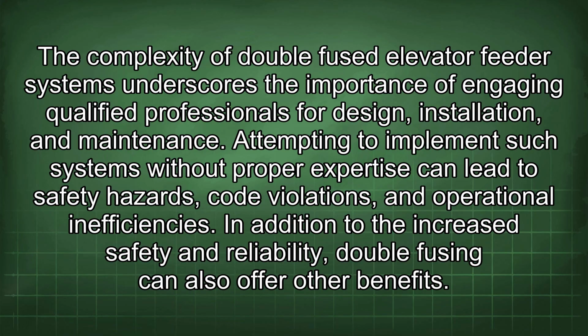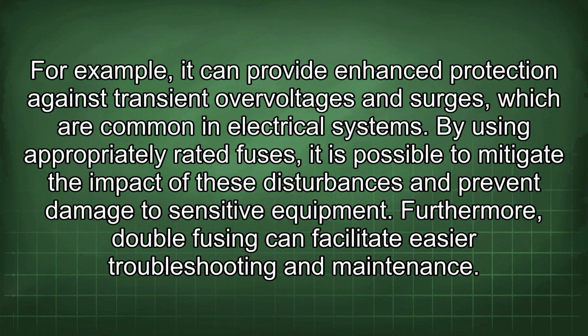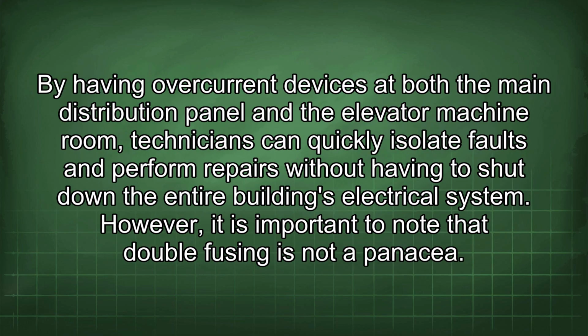In addition to the increased safety and reliability, double fusing can also offer other benefits. For example, it can provide enhanced protection against transient overvoltages and surges, which are common in electrical systems. By using appropriately rated fuses, it is possible to mitigate the impact of these disturbances and prevent damage to sensitive equipment. Furthermore, double fusing can facilitate easier troubleshooting and maintenance. By having overcurrent devices at both the main distribution panel and the elevator machine room, technicians can quickly isolate faults and perform repairs without having to shut down the entire building's electrical system.